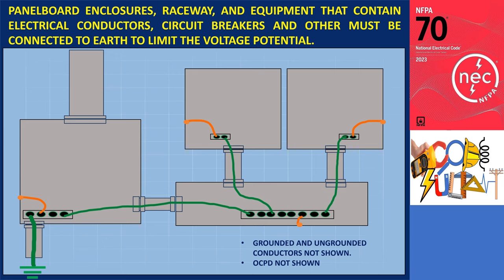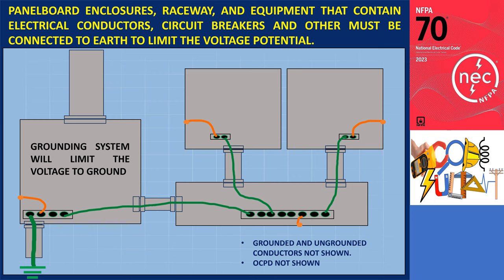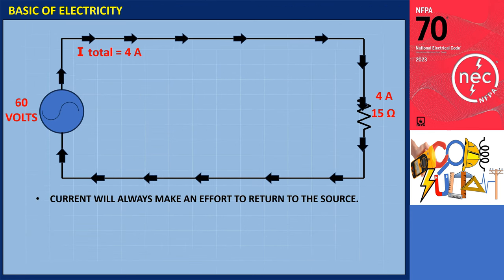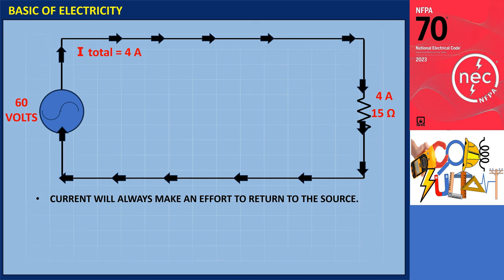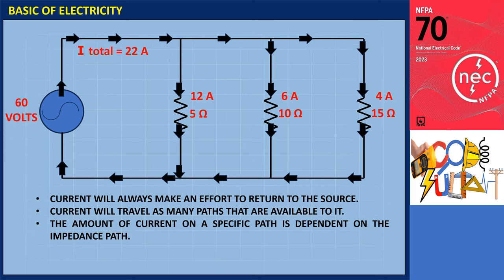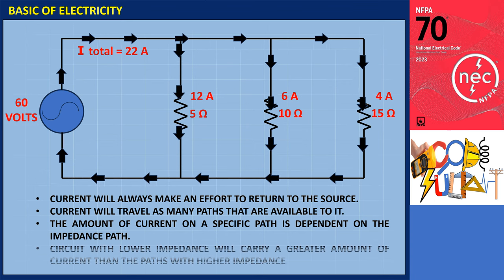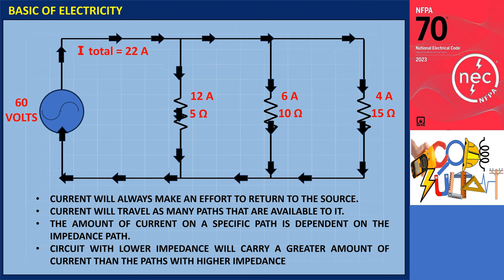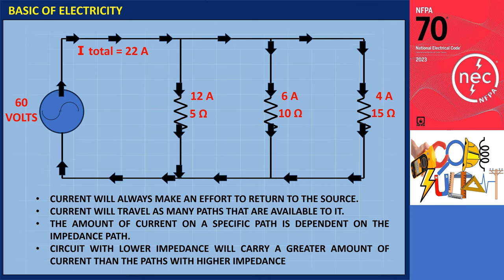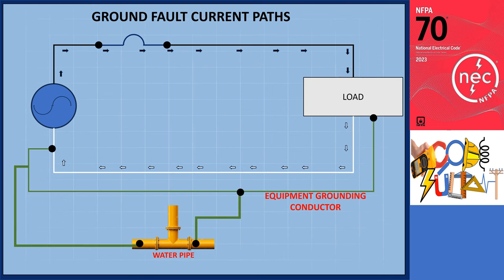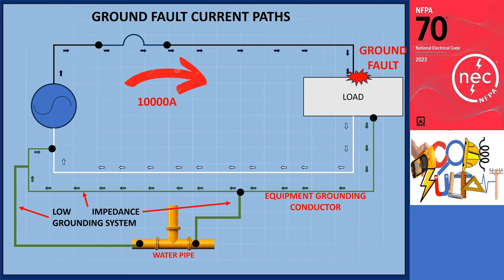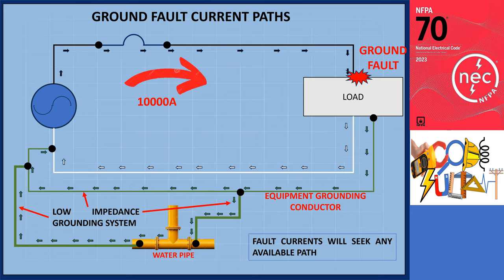If the installation of grounding complies with the prescriptive methods of this article, the grounding system will limit the voltage. When a fault or surge occurs, the grounding system redirects the excessive current to the ground, preventing it from causing damage or posing a risk to people and equipment. The term 'limit' is used because the grounding system will not eliminate the voltage to ground on the materials. Current will naturally flow through all available paths, dividing among them inversely proportional to the impedance of each path — so paths with lower impedance carry greater current.